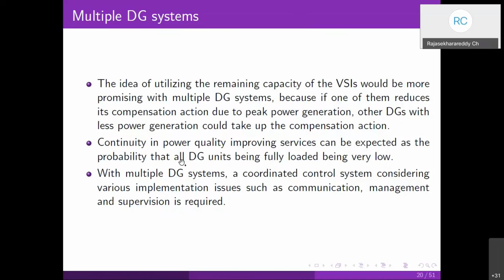Therefore, we can ensure continuity in power quality improvement services, because the probability that all the DG units are fully loaded is very low. With multiple DG systems, we need a coordinated control system, which has to coordinate with all the DGs in the microgrid. We would like to keep this control structure as simple as possible, so we need to eliminate inter-unit communication. For that purpose, we need a centralized control system, so that signals are sent to the individual inverters of the renewable energy sources, and they don't have to communicate with each other in order to provide compensation.